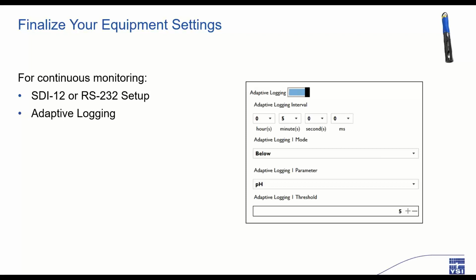An additional feature of sondes that is pretty useful is adaptive logging. You may find this under the advanced settings. This allows your sonde to increase its sampling rate to capture events as they happen if certain thresholds are met. Examples of this would be pH or dissolved oxygen dropping below 5 and wanting to record data at 5-minute intervals during these periods instead of a normal 15-minute interval that it may be set up for. If you elect to set up adaptive logging, be aware that the battery life estimates do not take this option into account, so you may not get data over the full range you're expecting, depending on how frequently those thresholds may be met.